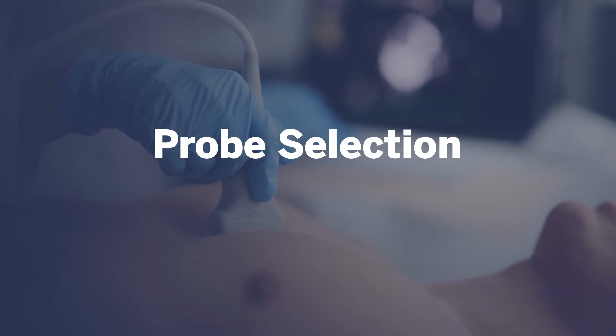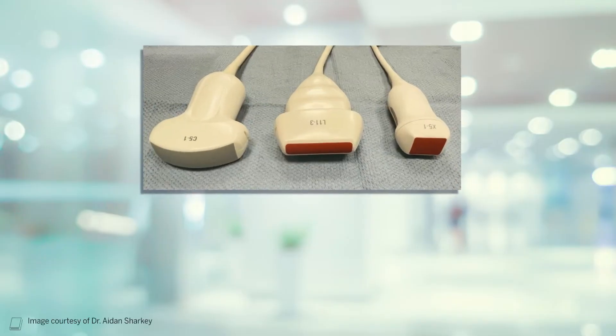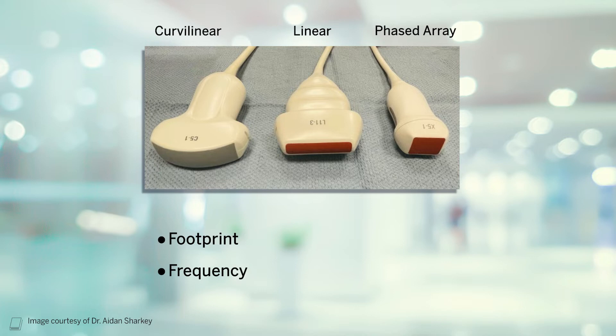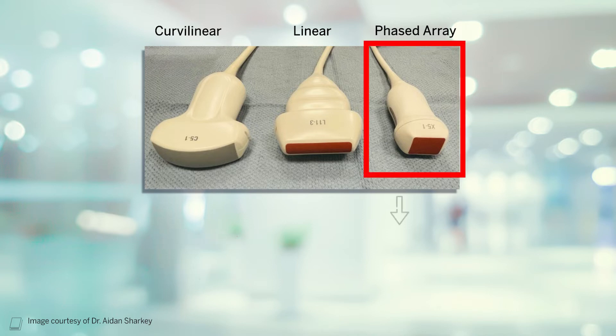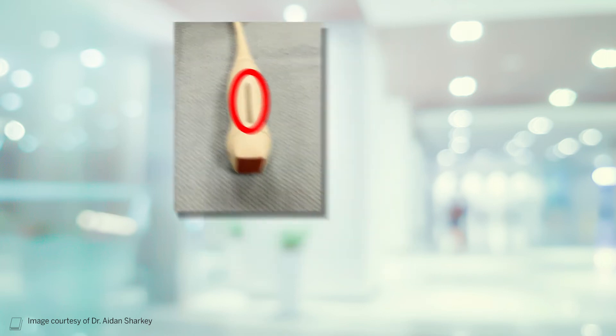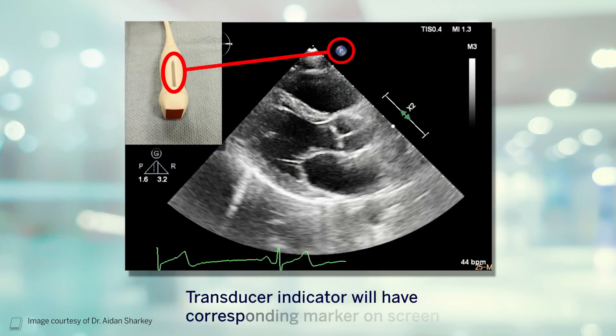We will now move on to probe selection for point-of-care ultrasound. In general, probes used for point-of-care ultrasound are classified as either curvilinear, linear, or phased array probes. The footprint of the probe and the frequency of ultrasound waves emitted are the major differing factors between probes. For cardiac ultrasound, we generally choose the phased array probe. This probe is chosen for its small footprint, along with its low frequency, thus giving good tissue penetration. For all ultrasound probes, it is important to make note of the transducer indicator on the ultrasound device and which side of the image this corresponds to on the screen. This becomes very important for correct anatomical display on our echo views.